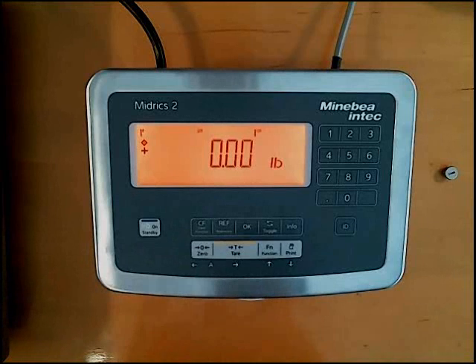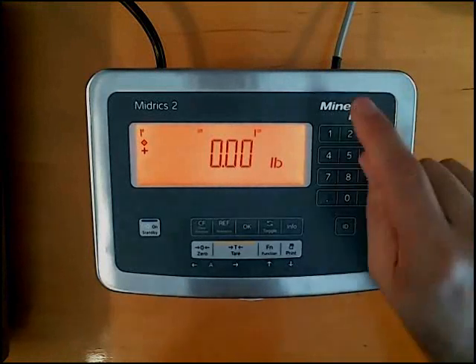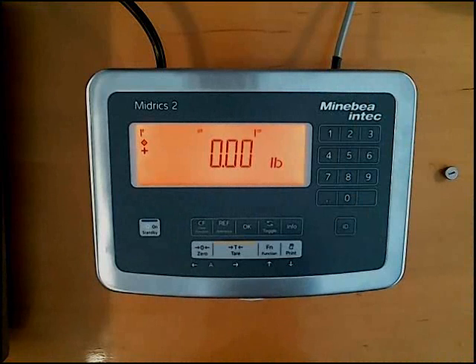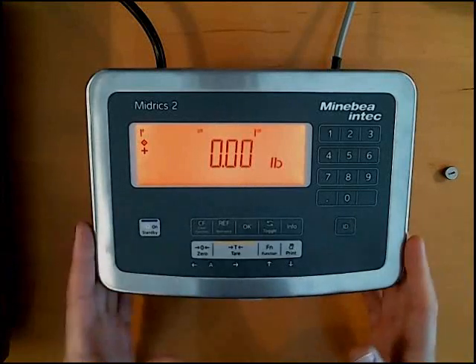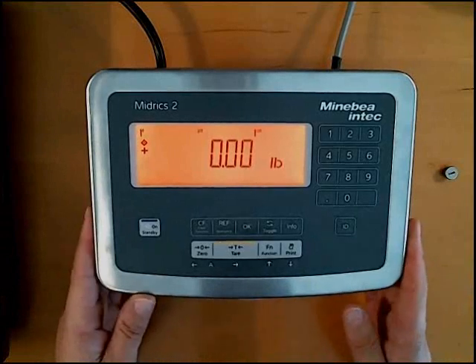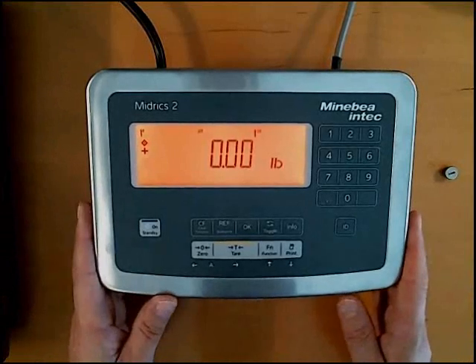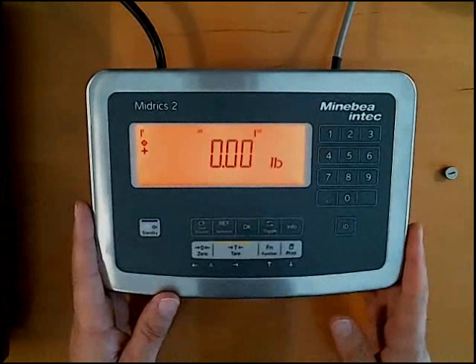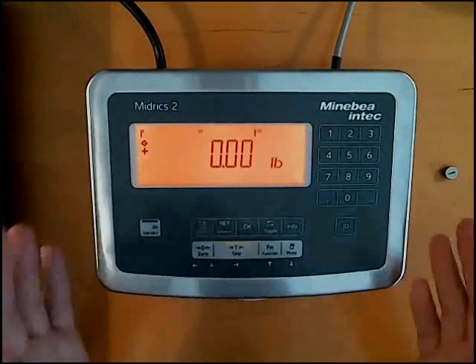The next thing we're going to do is calibrate the scale. Now this is the calibration in service mode. Remember, we have our switch in the service position. So we're going to go ahead and do the service calibration. When you do an initial calibration, you need to be in the service mode because the indicator doesn't really know what the weight should be. You're going to tell it. You're going to define what 5 pounds really is.